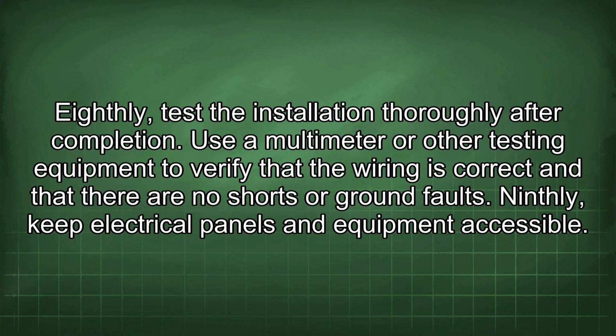Eighthly, test the installation thoroughly after completion. Use a multimeter or other testing equipment to verify that the wiring is correct and that there are no shorts or ground faults. Ninthly, keep electrical panels and equipment accessible.